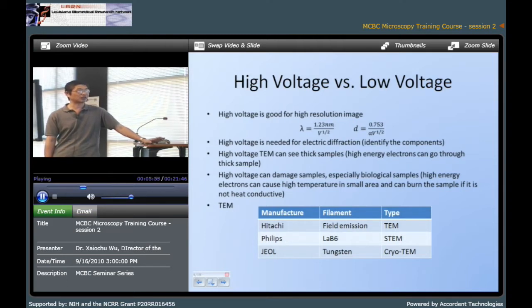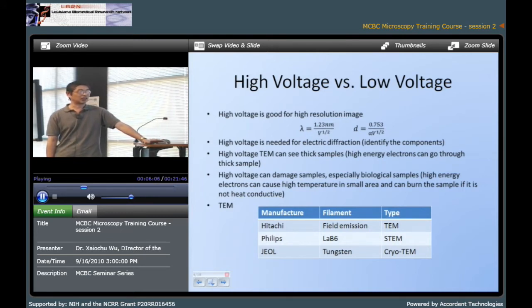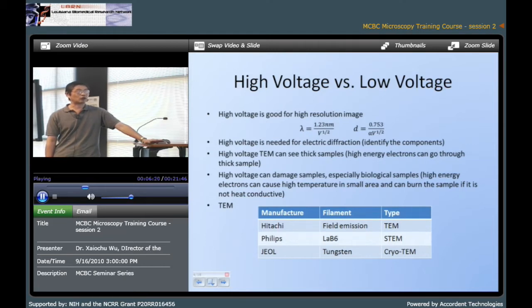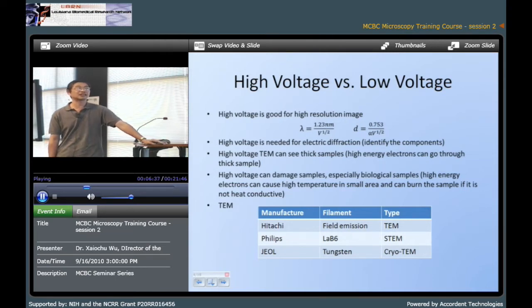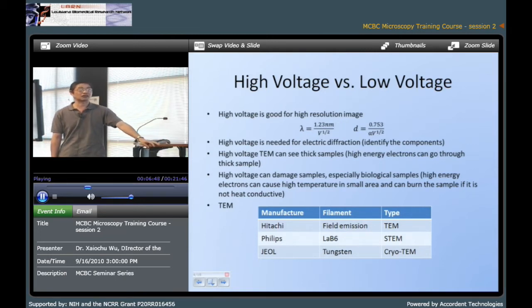For high resolution microscopy, we only use the parallelized beam in the center of the electron beam. In this case the aperture will be very small and magnification will be very high. So LaB6 or field emission is necessary because they are much brighter than tungsten. Also field emission has another advantage because it can make a very parallelized beam. So I think the best option, if you want to see the atoms in your material — which is basically for material science research — is field emission. LaB6 is also available.